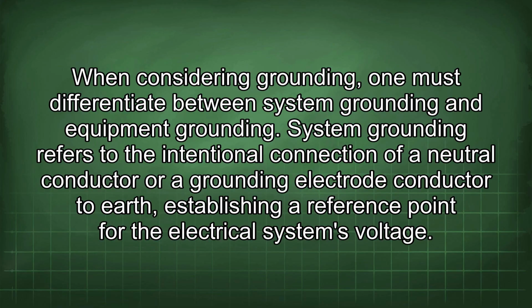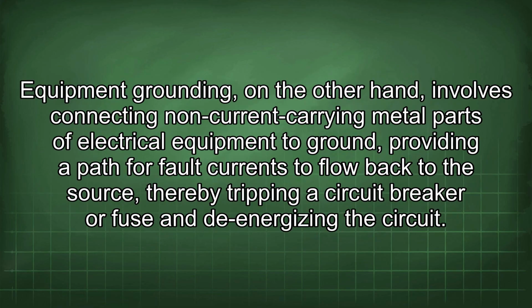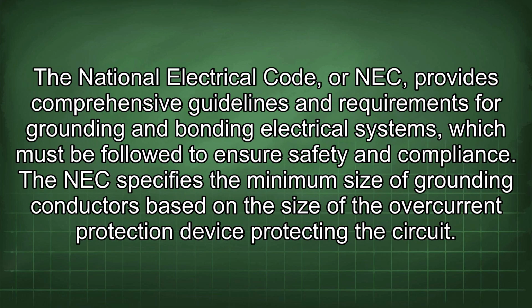System grounding refers to the intentional connection of a neutral conductor or a grounding electrode conductor to earth, establishing a reference point for the electrical system's voltage. Equipment grounding, on the other hand, involves connecting non-current carrying metal parts of electrical equipment to ground, providing a path for fault currents to flow back to the source, thereby tripping a circuit breaker or fuse and de-energizing the circuit. The National Electrical Code, or NEC, provides comprehensive guidelines and requirements for grounding and bonding electrical systems, which must be followed to ensure safety and compliance.